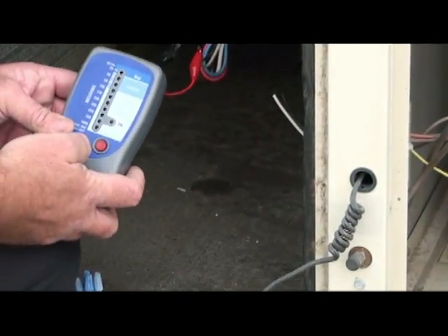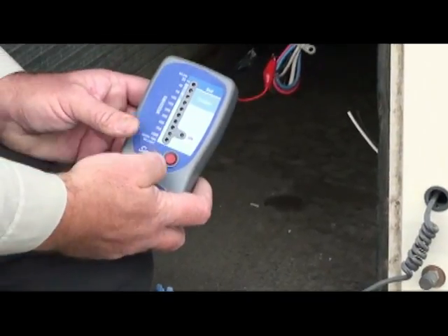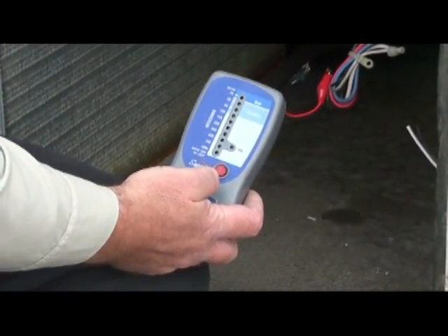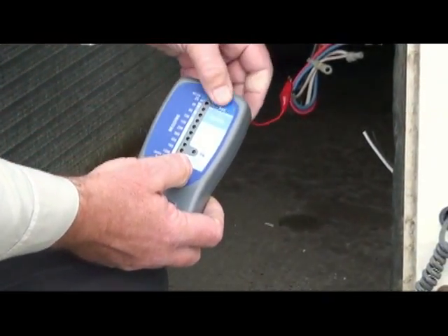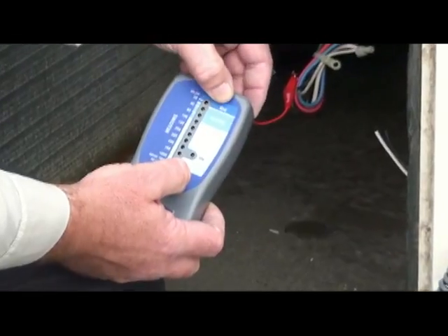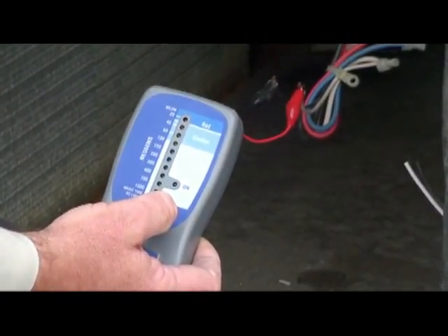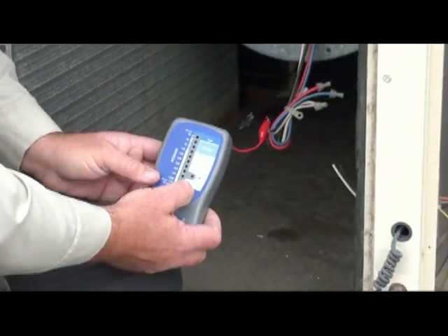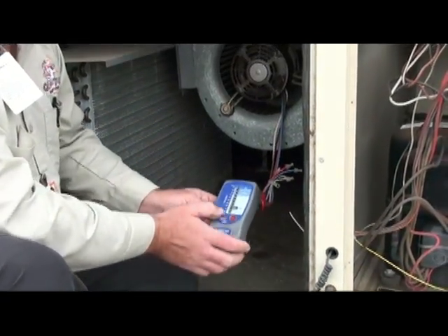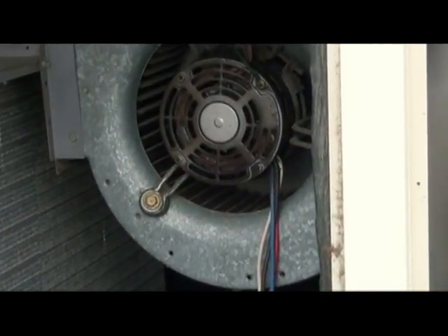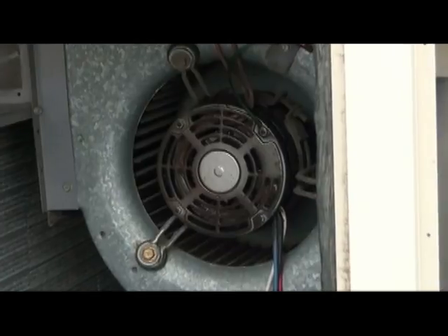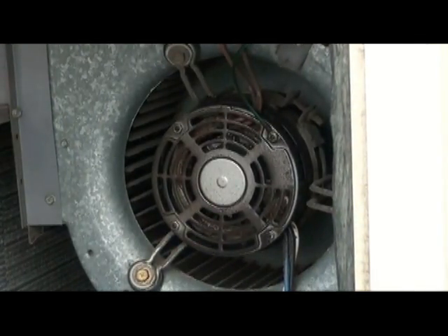By hooking up the mega ohm meter, you can see on this particular blower motor that we're checking the resistance on the windings. And when you energize this mega ohm meter, it shows that the insulation is in the bad range, which means that the insulation on these windings has decayed to a point which is compromising the motor itself. Over time, that winding can heat up because the insulation is not there any longer. That winding will fatigue and over time can break, making the motor useless. It will not work at that point.